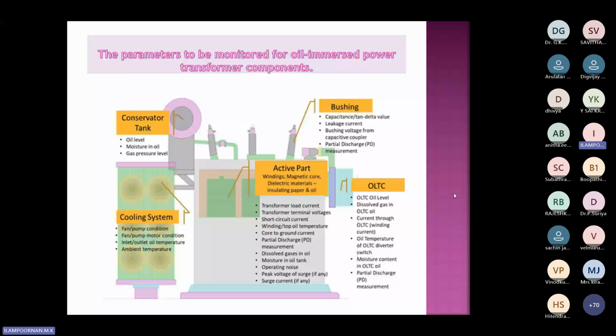Suppose one of the transformers is operating on a different voltage level, what will happen? I think it can't be parallely operated. The main condition is the transformer voltage should be same. If not, an internal current will flow between the transformers. If it is there, what will happen? The losses will increase, and there will be circulating current between the transformers, which leads to losses.